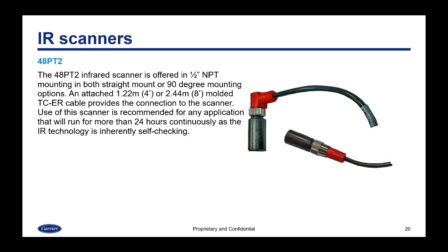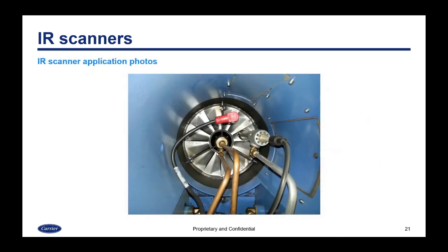The 48PT2 infrared scanner is offered with a 1/2-inch NPT mounting in both a straight or a 90-degree version. And it has a 4-foot or 8-foot molded cable to provide the connection to the scanner. This is the scanner we recommend that you use for any application that will run for more than 24 hours continuously, as the IR technology is inherently self-checking. Here's an image of an IR scanner mounted.